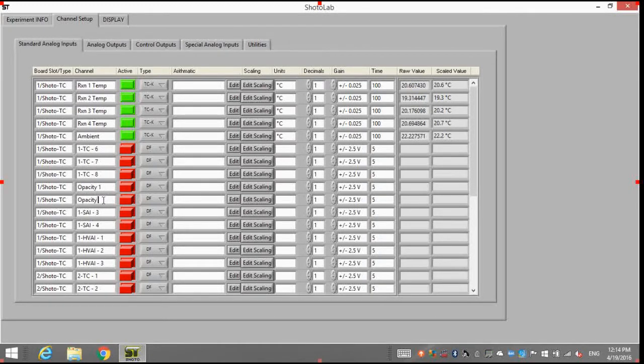And just like the thermocouples, first name the channels, I'm going to keep things simple and follow the same routine as with the TCs. The first reactor I'm going to call opacity 1, the second one opacity 2, the third one opacity 3, and the fourth one opacity 4. Since I'm reading voltages on these, I don't have to change the channel type. And the maximum voltage that these will read is 1.25 volts. So let's change the gains to get the best reading. Change the sample time to 100 to match that of the TCs. Change the decimals to be displayed to 3.